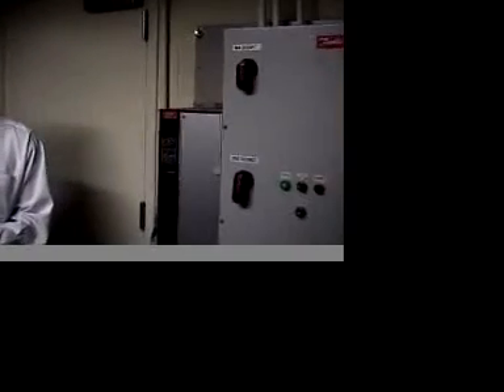So in the middle of wintertime, you should be up very high, and in the middle of mild summer days should be very little. Which is why I'm asking: this is a mild day today, yet we're running 50% on the pump. When we had mild days and weren't running air conditioning because it was cool, we were down to 30%. Why would we be so much higher on the heating side than the cooling side? No idea. All I can tell you is that you've got a load someplace, you've got some rooms that are asking for water right now, whereas with the cool days, we weren't asking for a whole lot of chilled water.